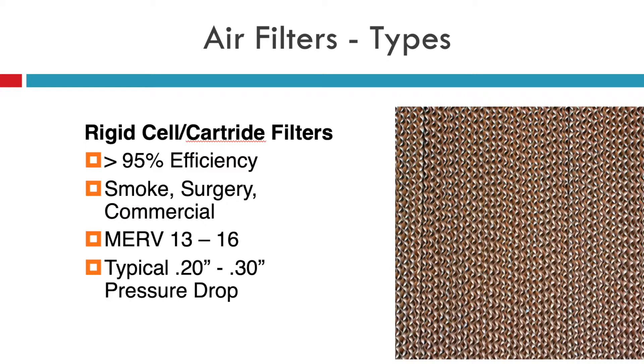Moving up to rigid cell or cartridge filters — like the cells inside an AccuClean that American Standard makes — they typically have some sort of pre-filter and then the rigid cell or cartridge filter. They tend to have really high efficiency and fall into the MERV 13 to 16 range. These are used in surgical rooms and commercial applications and do a great job removing smoke and odors. They have a slightly higher pressure drop, typically 0.2 to 0.3, and definitely have to be designed around. Putting this into a duct system without planning will likely change the volume of air and impact comfort.